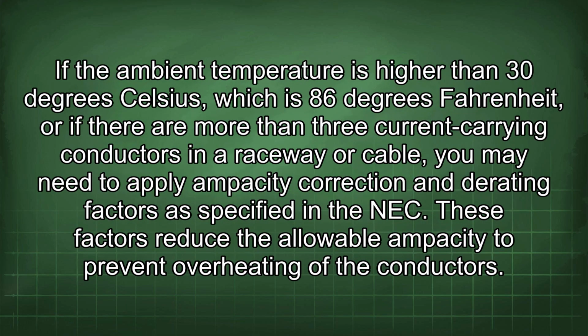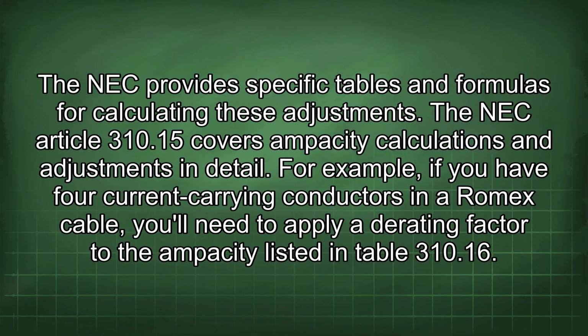If the ambient temperature is higher than 30 degrees Celsius, which is 86 degrees Fahrenheit, or if there are more than 3 current-carrying conductors in a raceway or cable, you may need to apply ampacity correction and derating factors as specified in the NEC. These factors reduce the allowable ampacity to prevent overheating of the conductors. The NEC provides specific tables and formulas for calculating these adjustments. The NEC Article 310.15 covers ampacity calculations and adjustments in detail.